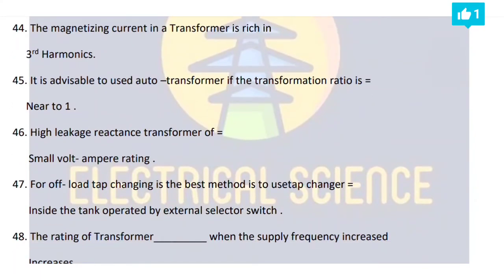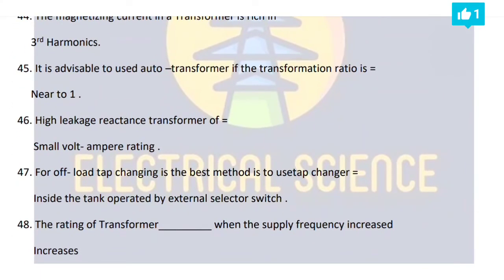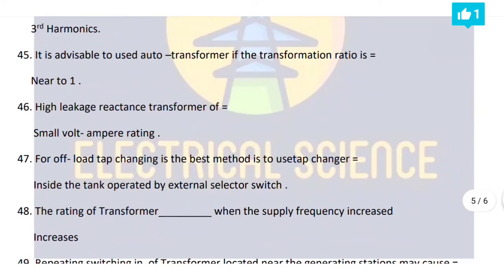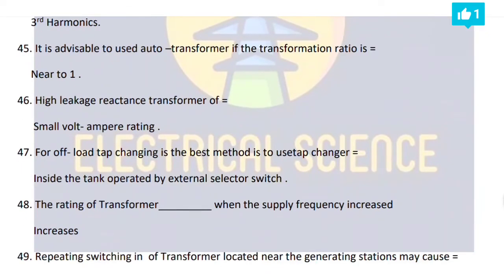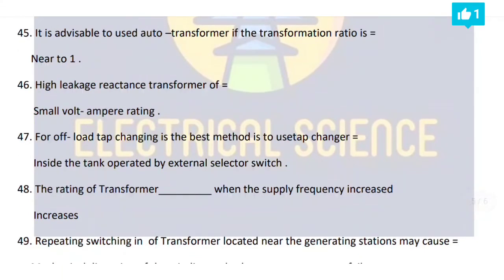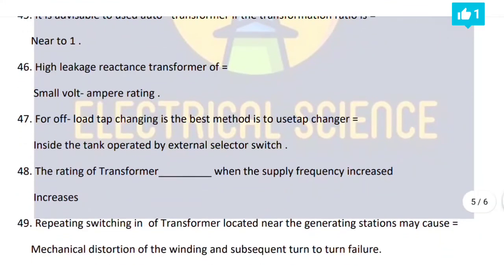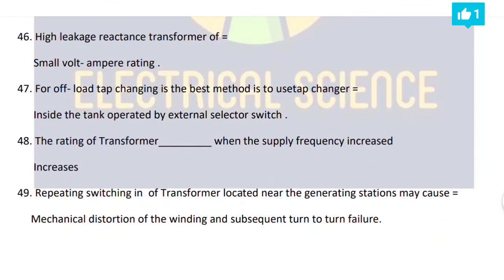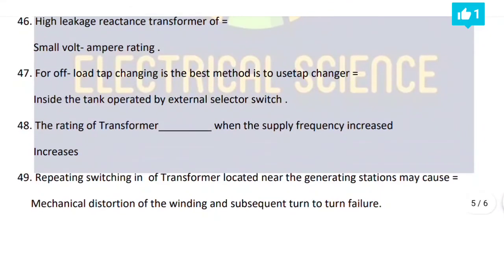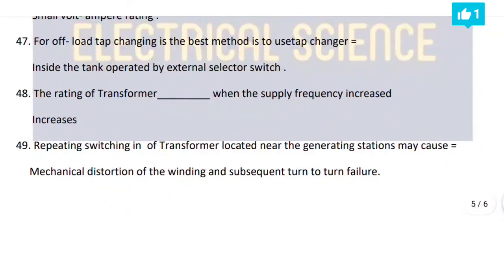46th point, high leakage reactance transformer of small volt ampere rating. 47th point, for off-load tap changing, the best method is to use a tap changer inside the tank operated by an external selector switch. 48th point, the rating of a transformer, I repeat it again, the rating of a transformer dash when the supply frequency is increased. As we increase the frequency, the rating of the transformer also increases.